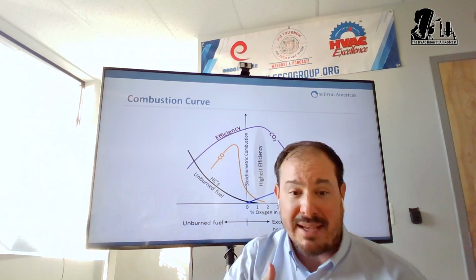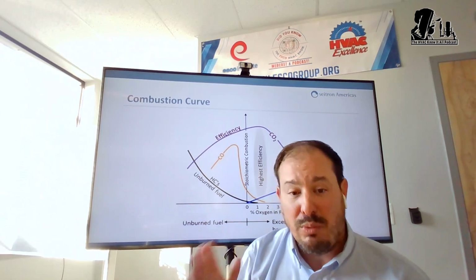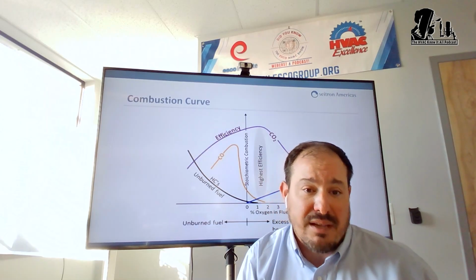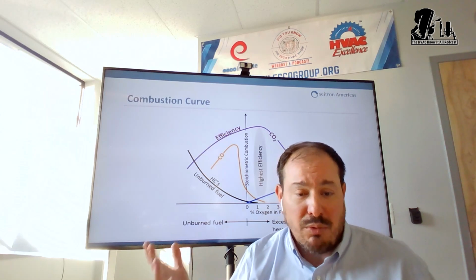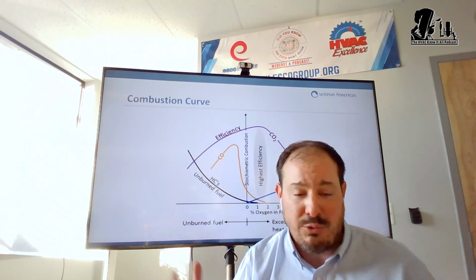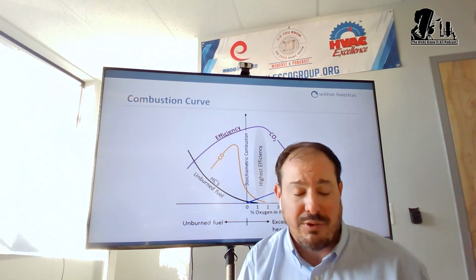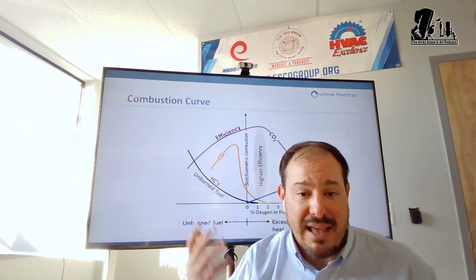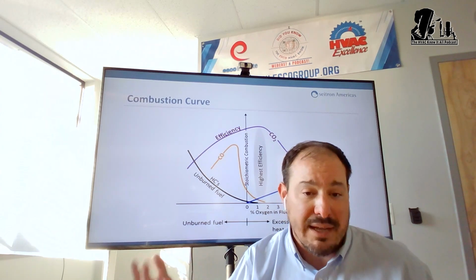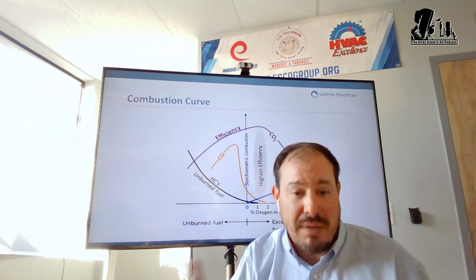And once you start bringing that back in, that's where all the problems occur, with things like burning out and rusting out igniters and heat exchangers and all that type of stuff, because the acidity in that gas that should be going out is coming back in and recirculating. So there's a variety of reasons why, not to get on a soapbox, I don't like PVC on the exhaust side. I don't like it at all. Well, number one, Schedule 40 is not rated for exhaust temperatures on a boiler or furnace. Number two, the acidity in that NOx starts eating away and discoloring that material. It's made for plumbing. It's not made for exhaust.